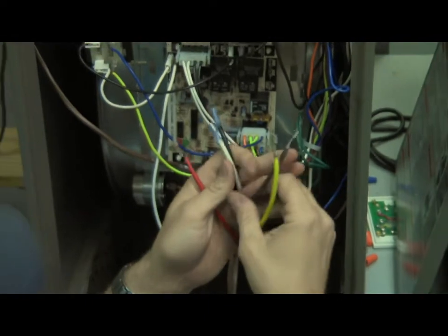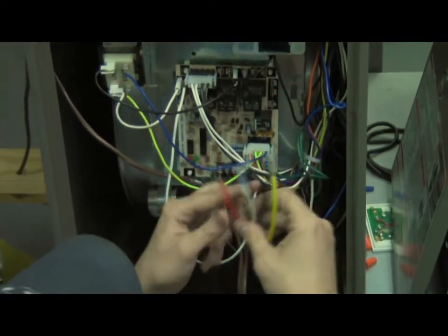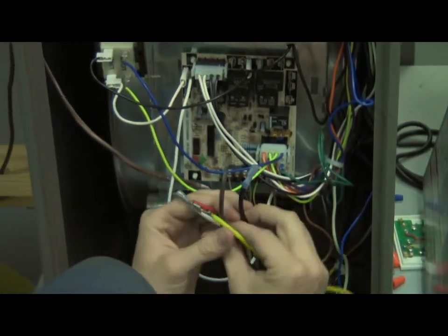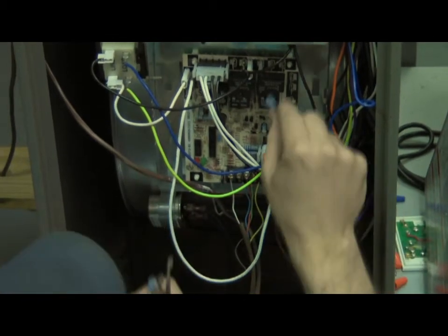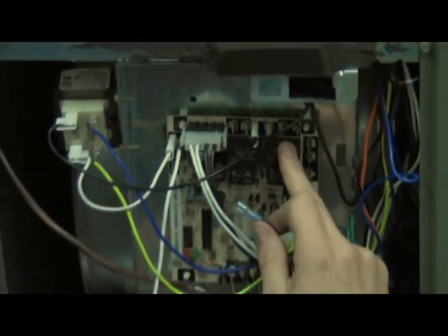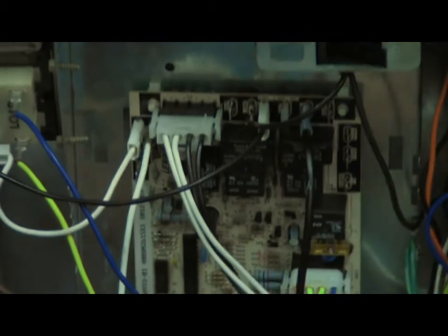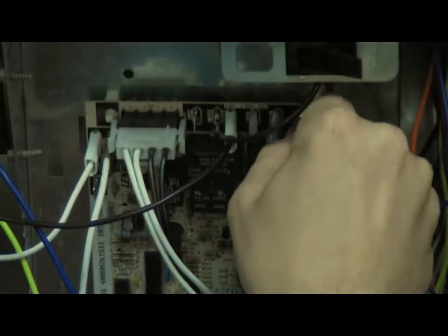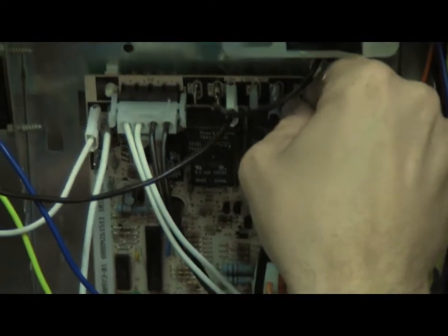Okay, next we're going to hook up the leads for the blower motor. Okay, we're going to use high speed for cool, and on the board here at the top it says cool, so we're going to put that there. We're going to use red, which is low speed, for heat. We're going to put that on the terminal that says heat.